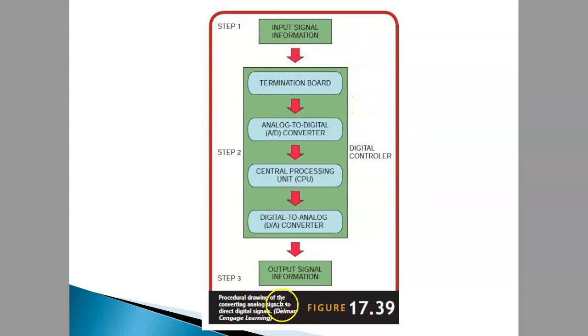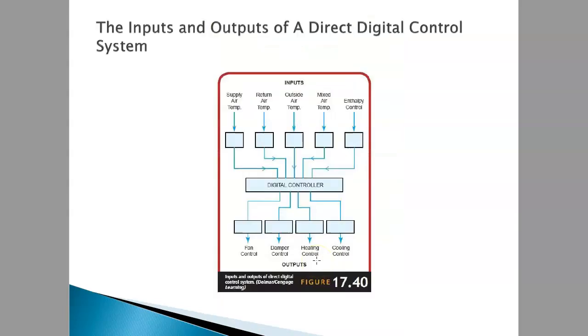Basically this is a procedural drawing of converting analog signal to direct digital signal. Input signal information, whatever sensor it has, and then it goes to the termination board. This is the direct digital controller or the CPU board, and then if it's an analog to digital converter, it goes to the CPU to process, and then digital to analog converter. It is converted to analog because this is analog. For example, you have a fan that is analog, so digital to analog, then the output will be the function.